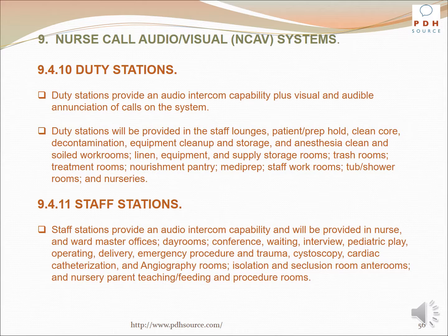Staff stations provide an audio intercom capability and will be provided in nurse and ward master offices, day rooms, conference, waiting, interview, pediatric play, operating, delivery, emergency procedure and trauma, cystoscopy, cardiac catheterization, and angiography rooms. Isolation and seclusion room, anterooms, and nursery parent teaching, feeding, procedure rooms.